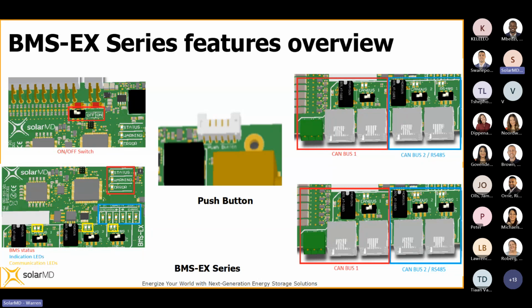The CAN bus termination switches, which you can see on the right-hand side of the slide, are necessary when it comes to CAN bus communication. It's basically a resistor that needs to be enabled at the end of the CAN bus line. Maybe this is too much detail for this session, but the point of that resistor switch, which you enable or disable depending on how many batteries you have, is to essentially prevent reflections on the CAN bus communication network. The signal, the transmission, is being sent out by the various devices, and if there is no termination at the end of the CAN bus line, that signal is reflected back up the line much like an echo, and that becomes destructive interference.